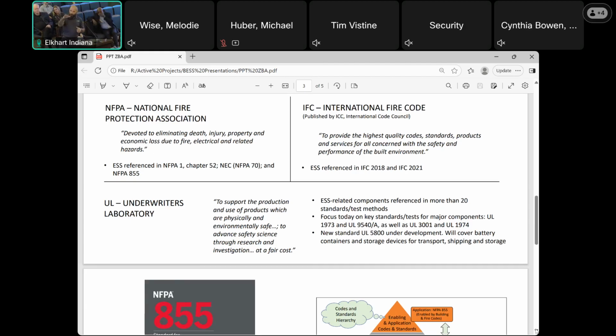But again, when you start looking at the code and how it works, not only on the 855, but then you start looking at the testing standard as how UL is applied to these specific technologies and integrations, you start recognizing that over the last several years - and I started doing this back in 2017, 2018 - we're now getting to the point where that propagation, we're having a very difficult time getting propagation when we look at these tests. And it's not just our lab, it's their lab as well. There are other nationally recognized testing labs across the country doing the same test, and we're not getting that outward propagation.